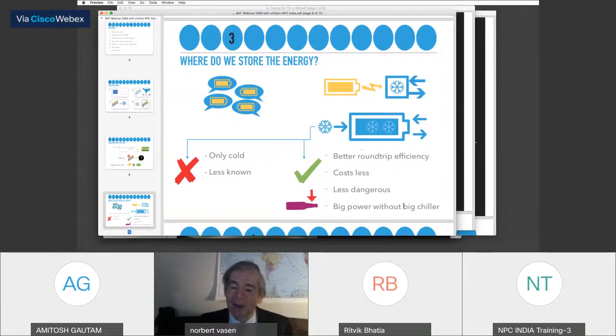Another important thing is that if you store electricity, you still need to dimension your chiller for peak demand. But if you have an ice storage, you can have a smaller chiller, and then you have less capital tied up in the chiller - as long as the ice storage can meet the peak demand. This big chiller is a lot of capital, and it's like a bottleneck in the whole system.